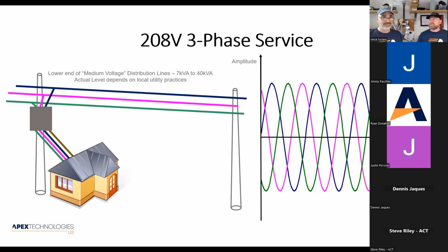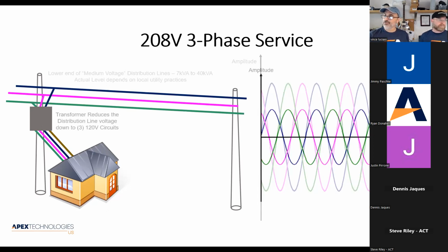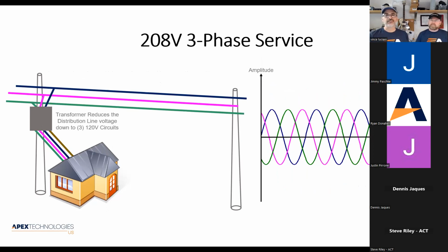Like if I wanted 3-phase at this house, I couldn't get it because I've only got 1 phase up there on the line. But if you have a rather large estate and the power company just happens to have all 3 phases available to you, the contract engineer or the electrical contractor may choose to power it off of 3 phases. And we shouldn't really get bent out of shape. It's really not all that daunting. All it means is that you're pulling from all 3 phases that are coming from the power company on those transmission lines. You're going through a transformer and you're knocking it down to 120 volt phases, right?